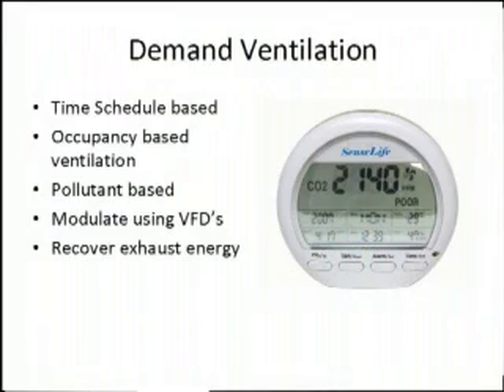Modulating, what we're talking about there is the exhaust and the supply air to the facility. And a very powerful technique is to use the VFDs that we showed there, the variable speed drives, to again get that savings while getting a handle on the ventilation.